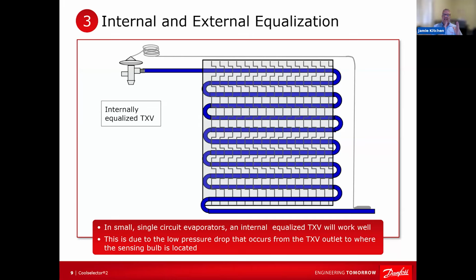So as long as the pressure where the sensing bulb is pretty darn close to the pressure leaving the TXV going into the evaporator, on either end of the evaporator, let's put it that way, inlet and outlet, as long as they're pretty close, no problem. You can use an internal equalized TXV. All right. And these are like small single circuit evaporators. The overriding factor is you do not have a refrigerant distributor.